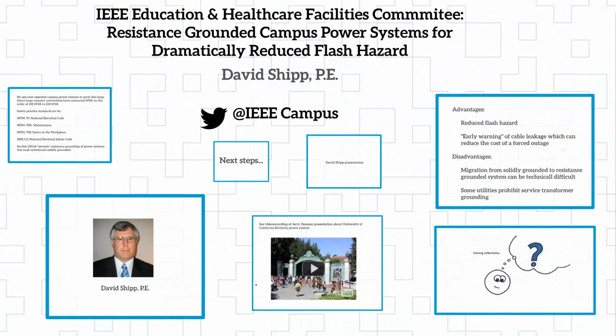It was worse. And if you're doing any service work in a cabinet and cause an arc flash event, it's going to be worse. My biggest problem was with all the arc flash studies we've been doing through the last 10, 15 years before I left Eaton, was a very common hospital or facility. They'll have a 480 volt transformer, 2000 kVA, for example, 4-wire, solid grounded, and they run 277 volt lighting. So here's a 2000 kVA transformer, and there'd be 5% of the load will be 277 volt lighting connected line to neutral. And if I have line to neutral loads, you must solidly ground to be able to supply the line to neutral loads.